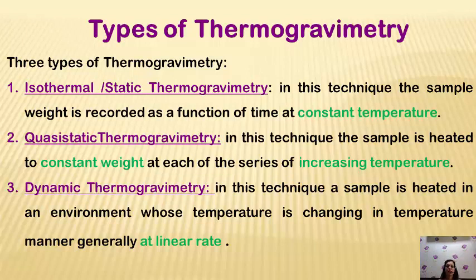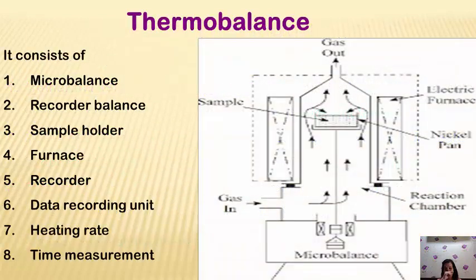Third is dynamic thermo-gravimetric analysis, where the sample is heated in an environment whose temperature is changing in a linearly programmed manner. The main component in thermo-gravimetric analysis is the thermo-balance, where the sample is kept in a container with a thermocouple near it. You also have a micro-balance, recording balance, and sample holder. These are the furnaces and the data recording unit. You have to maintain the heating rate and time measurement.